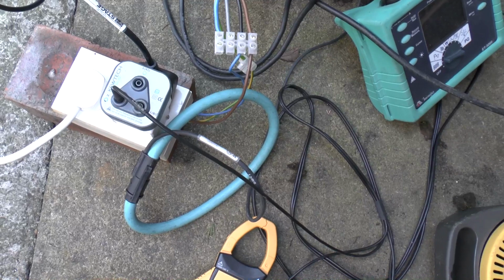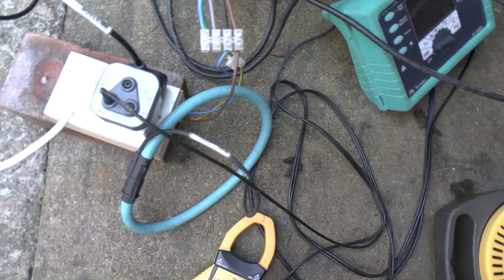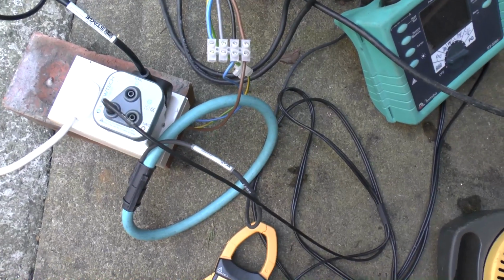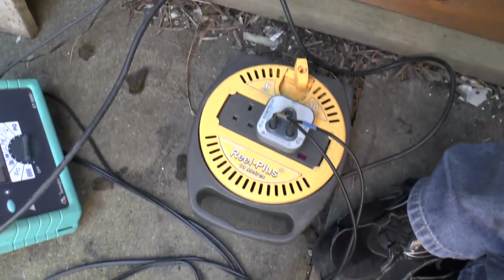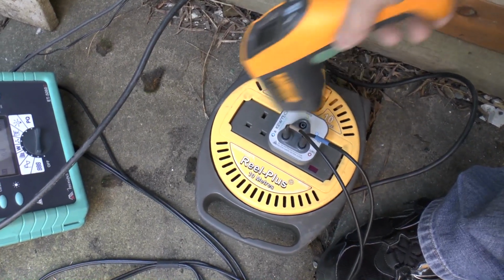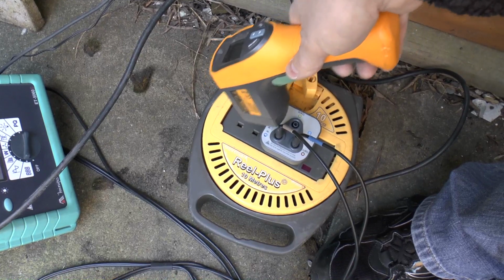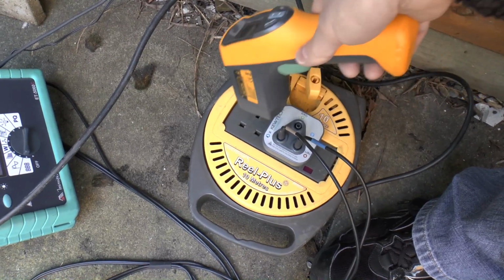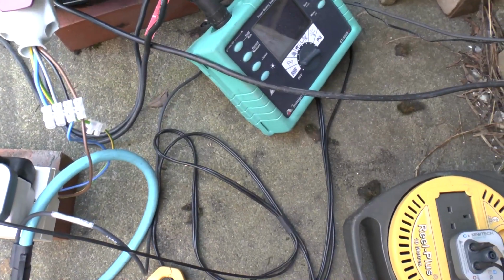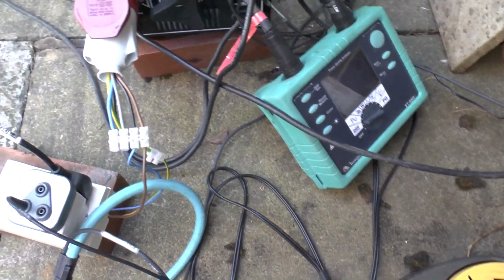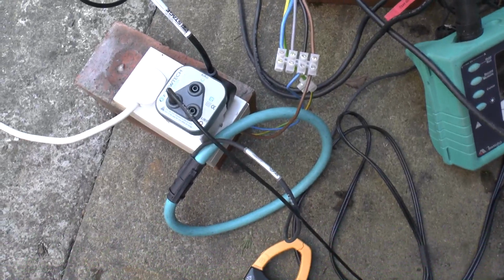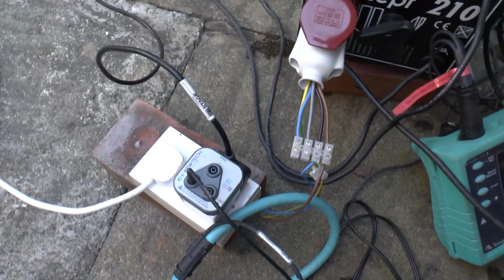That's why I'm measuring on the neutral side, and that's also why I've got the live and neutral connections the wrong way around on the measuring device. I'm using the live point as a reference, so that's 240 volts one way, and that's 415 volts. It'll all make sense in a moment.